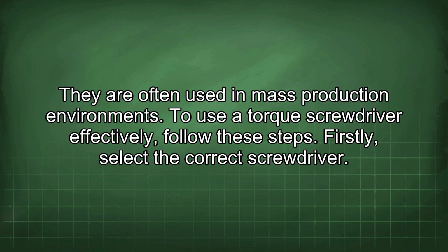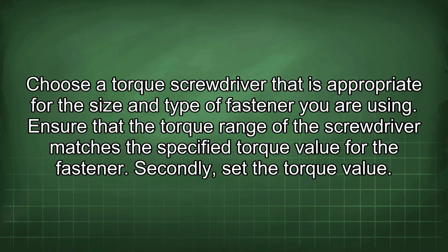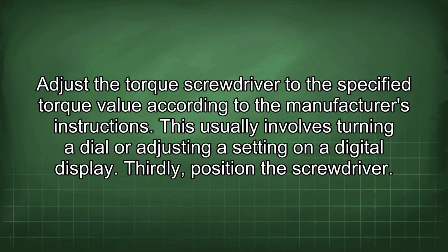To use a torque screwdriver effectively, follow these steps. Firstly, select the correct screwdriver. Choose a torque screwdriver that is appropriate for the size and type of fastener you are using. Ensure that the torque range of the screwdriver matches the specified torque value for the fastener. Secondly, set the torque value. Adjust the torque screwdriver to the specified torque value according to the manufacturer's instructions. This usually involves turning a dial or adjusting a setting on a digital display.